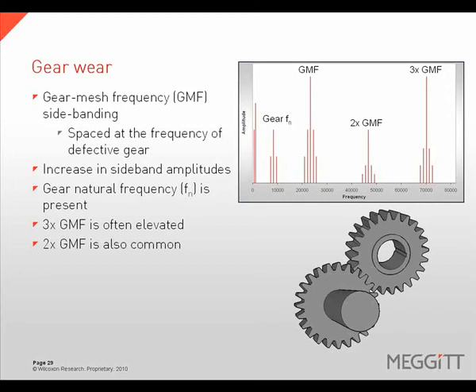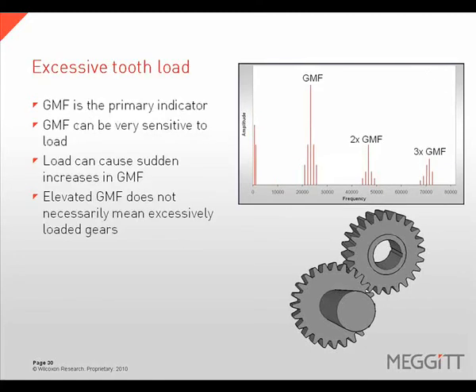Gear wear is characterized by elevated levels of gear mesh frequency and harmonics, with sidebands spaced at the running speed of the defective gear. As gear wear progresses, sideband amplitudes will increase as well as the number of sidebands. The gear natural frequency can be present, and the 2 and 3 times gear mesh frequency amplitudes are often elevated. Gear mesh frequency is the primary indicator of excessively loaded gears, and it can be very sensitive to load, causing sudden increases or decreases in amplitude as load changes.